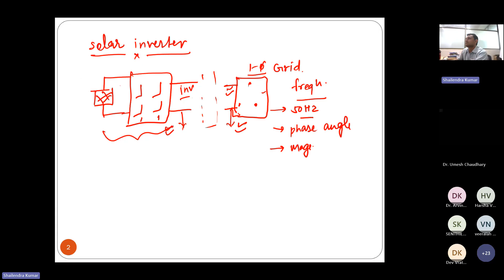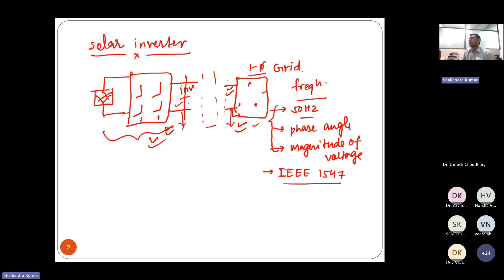So let me tell you, there is one standard known as IEEE 1547. This has given these three parameters. If you want to connect your inverter with the grid, you have to match the inverter output with these parameters. It's not that you generate some other voltage, frequency, and angle and connect the inverter with the grid. No. So if you bring one inverter or purchase one inverter and put it directly to this unit, it will not function. Right? Simply, if I bring some raw solar inverter and plug it into the grid, you might think it starts generating power and injecting power to the grid.